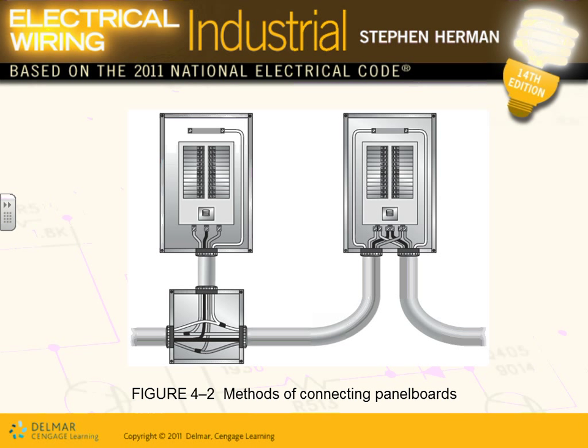Why doing it this way? Why do people do it this way? Cheap, easy. This is more economical. Contractors tend to do a lot of things like this. They take a feeder and they feed multiple panels. But remember, if the feeder is 225 amp, I can't pull more than 225 amp out of the whole system.